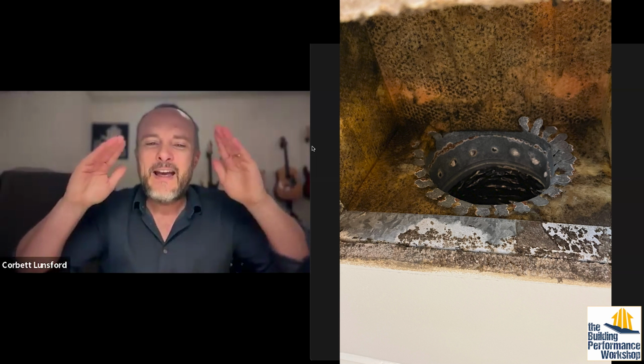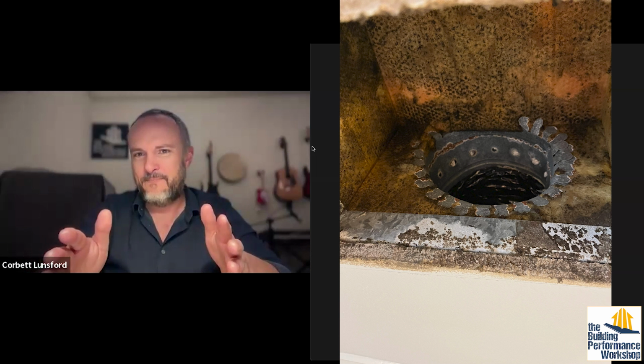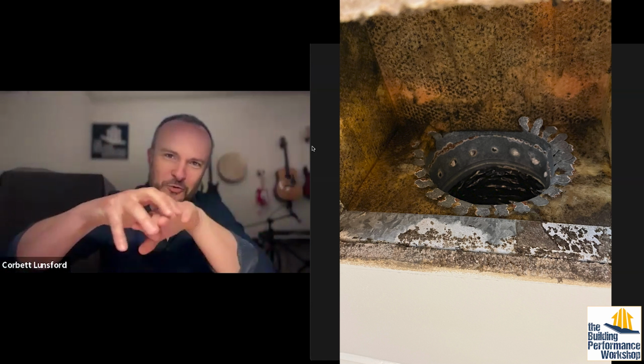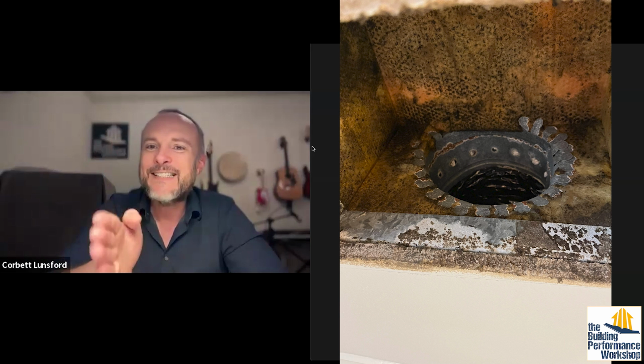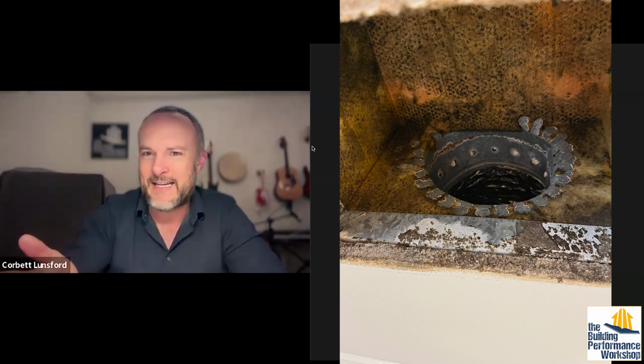So, can you first tell us why we are putting boots? The boot is the box that intercepts the drywall, right? That we're going to put the grill up. Yep. Why does this boot have insulation that is exposed to the airstream instead of being behind the sheet metal? So it was originally designed for noise dampening properties to try to reduce the noise level of the fan when it turns on. It's common for vent boots to sweat in an attic, especially in the southeastern region, humid climates, like down in Florida, very common. And when there's air leakage at the vent boot because it hasn't been sealed with mastic and hasn't been properly insulated, as the air is leaking into the insulation, it's actually degrading the R value more quickly.